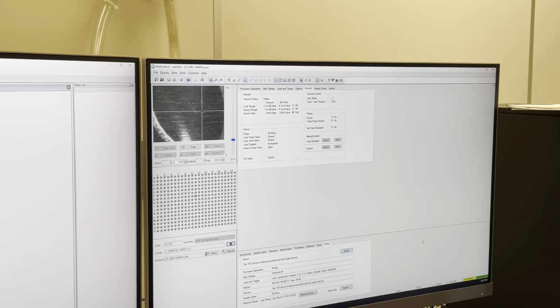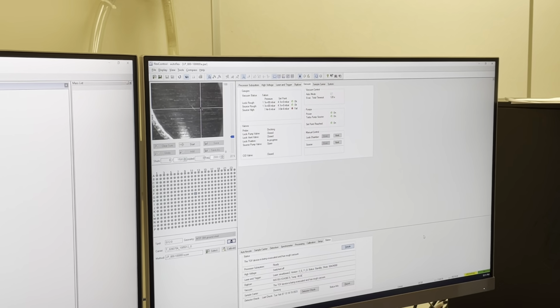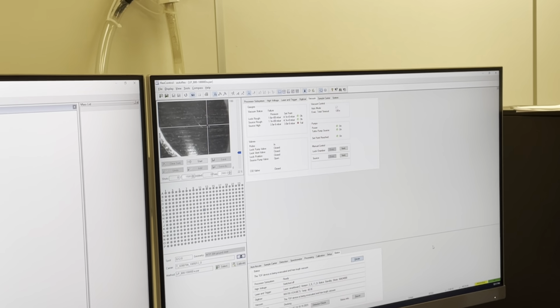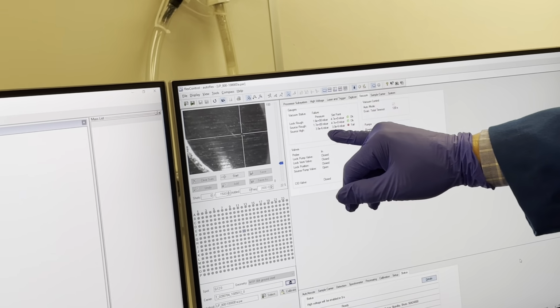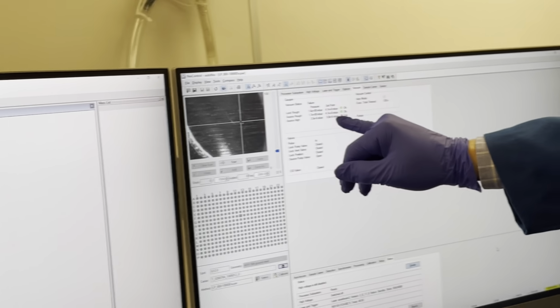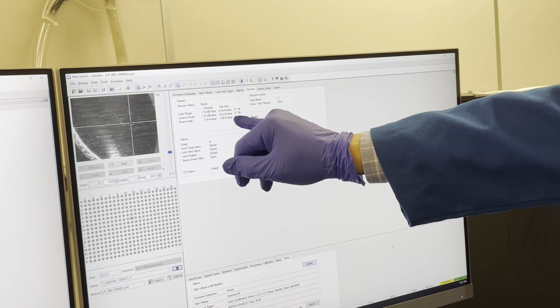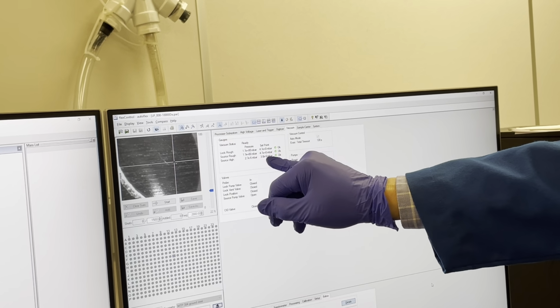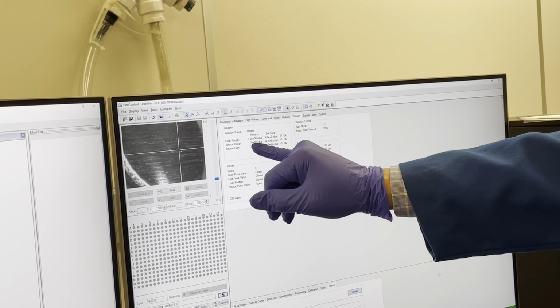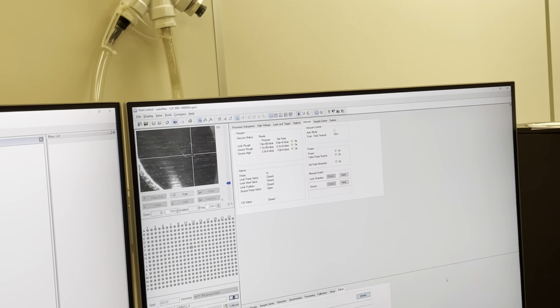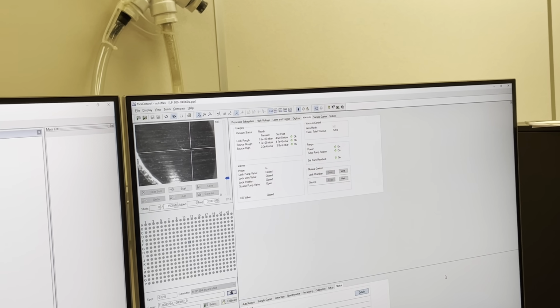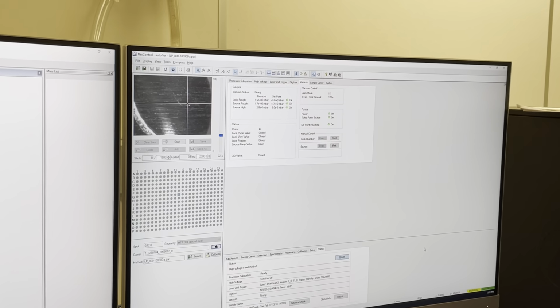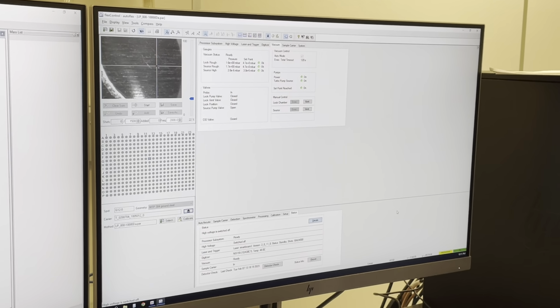So it will come down to 10 to the power minus 7. Okay. I like it to be in the 10 to minus 7 range before we go to the next step. Right now you see it's already green, but this is below the set point, and this is not good enough. I like this one to be in the 10 to minus 7 range. So be patient. Wait for another 30 seconds or even a minute.